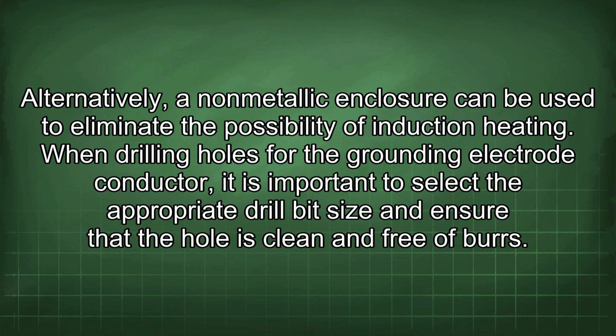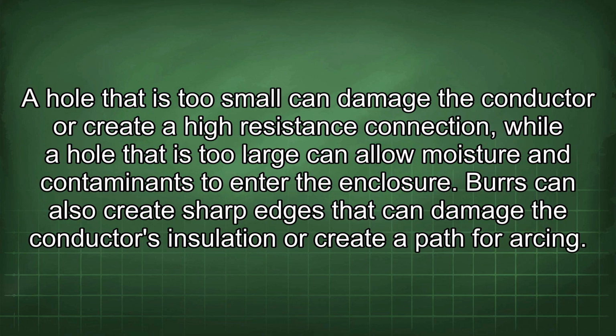When drilling holes for the grounding electrode conductor, it is important to select the appropriate drill bit size and ensure that the hole is clean and free of burrs. A hole that is too small can damage the conductor or create a high resistance connection, while a hole that is too large can allow moisture and contaminants to enter the enclosure. Burrs can also create sharp edges that can damage the conductor's insulation or create a path for arcing.